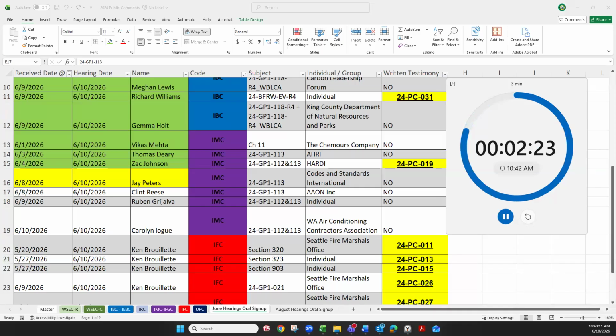First, the proposals would allow equipment using highly flammable A3 refrigerants to qualify through the Northwest Energy Efficiency Alliance Qualified Products List. This is an energy efficiency program, not a product safety certification program. It does not provide the same safety testing, factory inspections, ongoing compliance verification, or enforcement framework associated with UL 60335-2-40 certification. This creates concerning precedent.